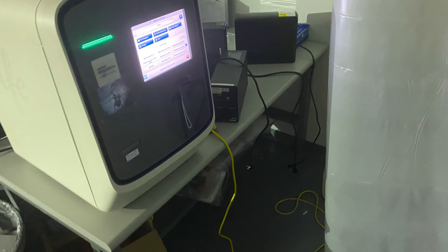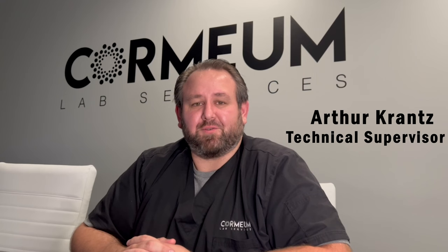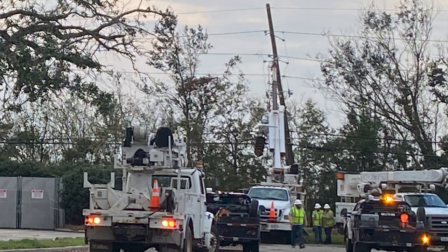After assessing the damage, we learned that the laboratory itself was in good condition. We were still able to keep things within range as far as temperature and humidity with backup generator power. With sensitive equipment, we wanted to make sure everything didn't fail, so we cut power to the rest of the building. We didn't run the AC anywhere else — we couldn't take the chance.